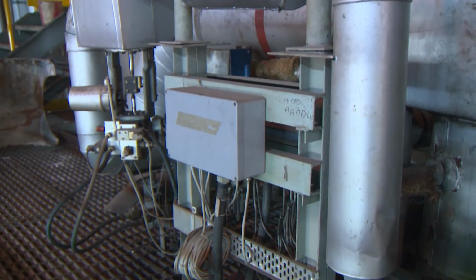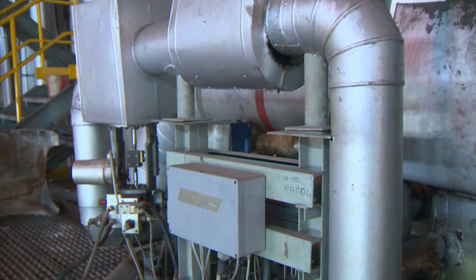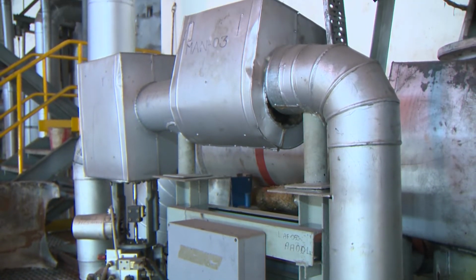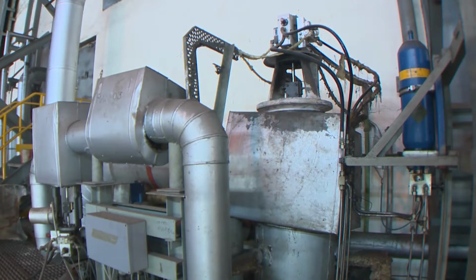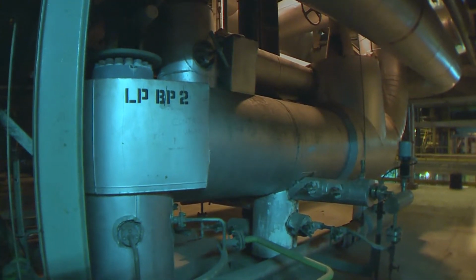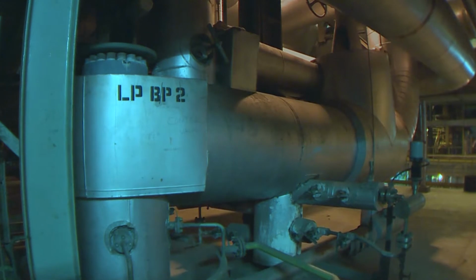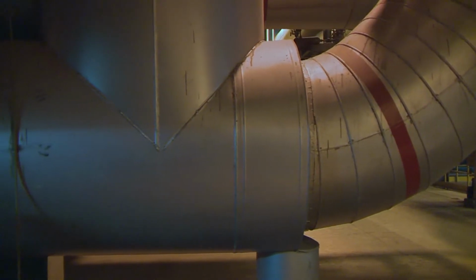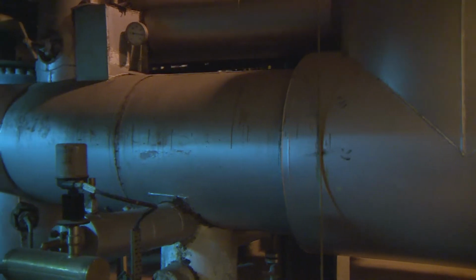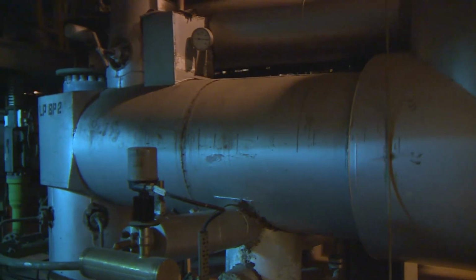High pressure and low pressure turbines bypass system. Specially designed hydraulically operated valves have been provided for the main steam to bypass the high pressure and low pressure turbines. These valves will be kept in operation during initial startup of the unit, tripping of turbo generators and house load operations.